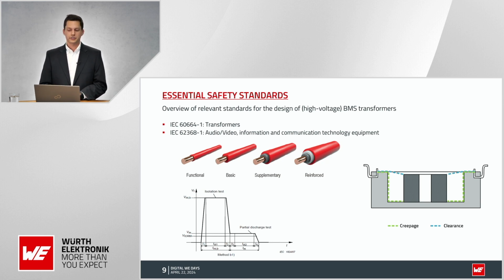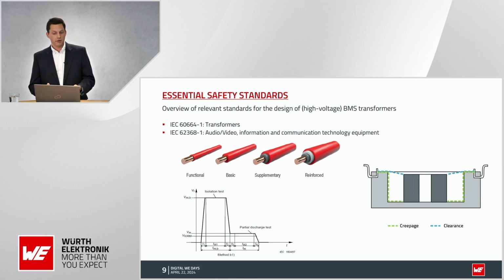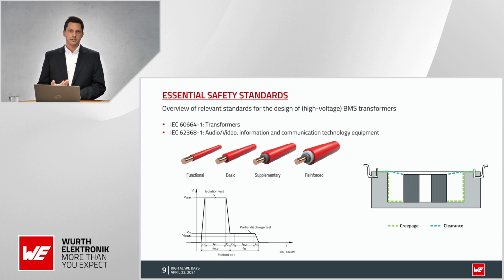The creepage distance is the shortest distance along the surface of an isolating material between two conducting parts. The creepage distance is determined in a similar way to the clearance distance. By looking at the overvoltage category, the degree of contamination, and the working voltage, the minimum creepage distance can then be calculated using table 17 of the mentioned standard.